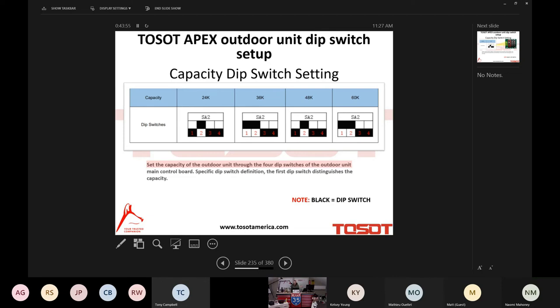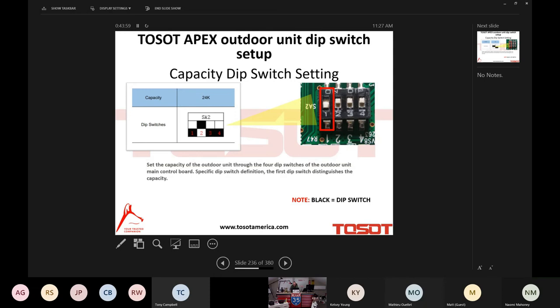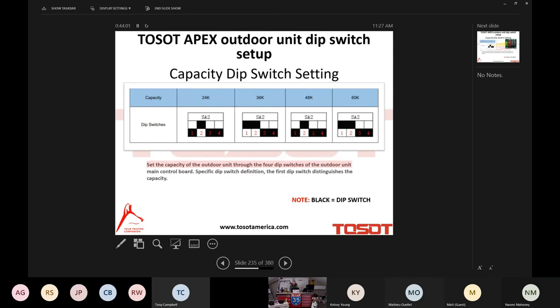And we're going to set the capacity with switch number one, right? So for the 2-ton, we want switch number one to be down. For the 3, we want it to be up. 4-ton, down. And this is just switch one, mind you. And for the 5-ton, you can see the switch is in the up position.